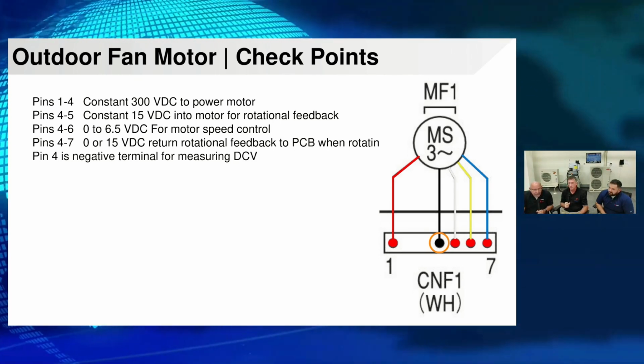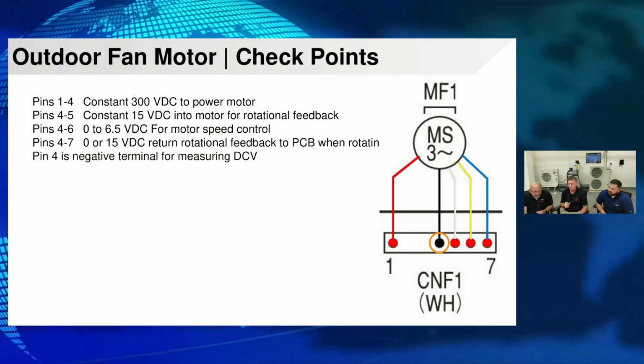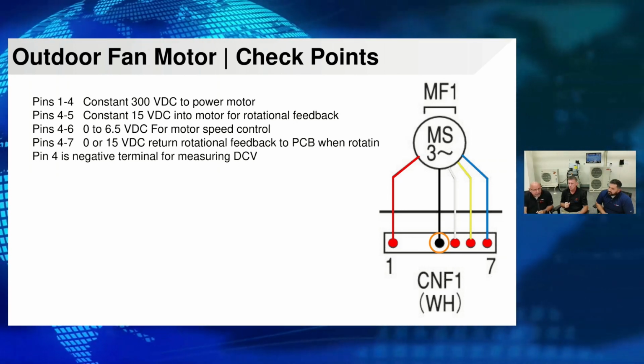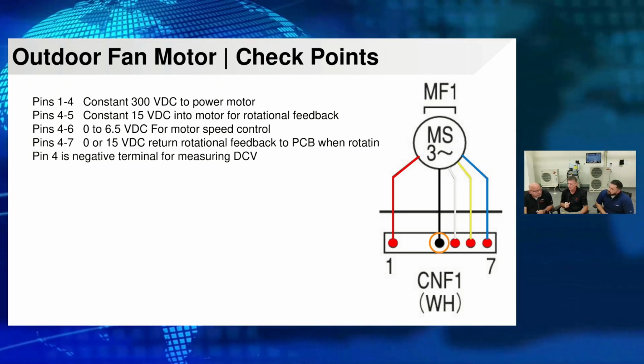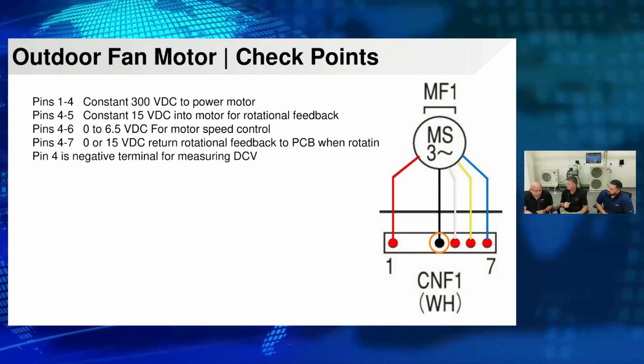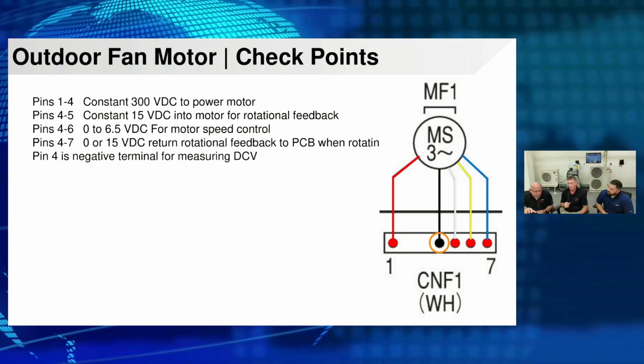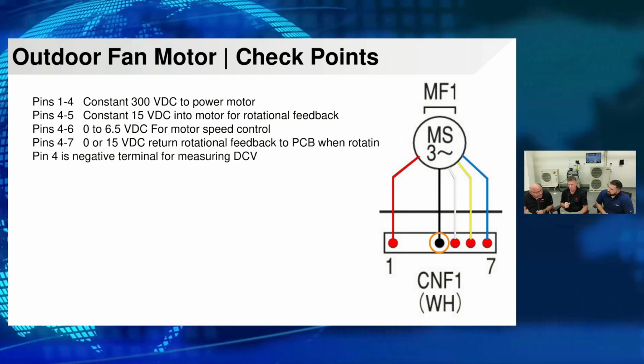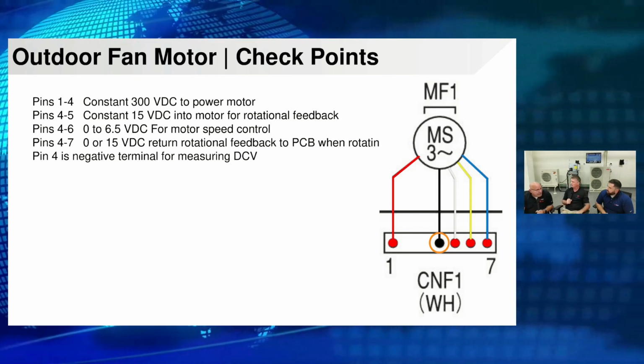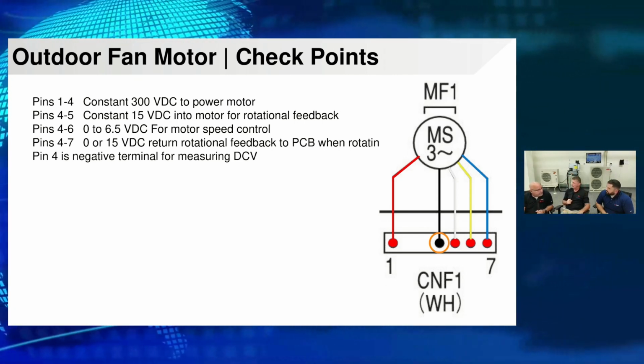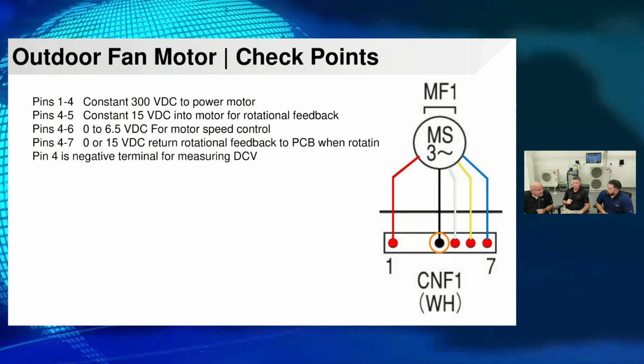The best way to check and test the signal is to stop the system from running, leave it powered up, put your leads across pins 4 and 7, and turn the fan blade by hand. Then you'll see the deflection - we'll generate our own voltage. That's it.